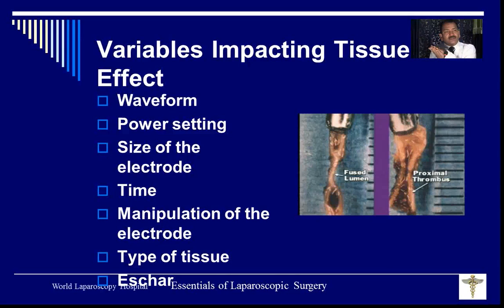You are holding the tissue, but it doesn't coagulate. Just like when your servant is making the food, and if all your vessels inside are black, that means she has burned a lot of things, and next day it has to be rubbed a lot to clean it. So making a lot of scar means you are not a good cook. If your instrument jaw is getting black scar formation, that means your intensity of the current is high, and you should decrease the intensity of the current. You are not cooking, you are burning.